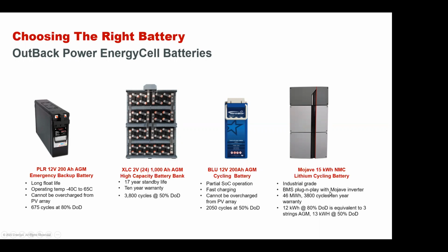The BMS makes a plug and play with the Mojave inverter. Basically, just hook up the 2 battery cables, the ground wire, and a CAN bus cable, and that's it. It's the only connections you have to make. We'll talk about that commissioning in just a moment. And then the 12 kWh at 80%, which is our recommended depth of discharge, is 12 kWh. That's equivalent to 3 strings of AGM batteries, which is about 13 kWh. So you get a little bit more kWh with 3 strings, but think of it as 3 strings of battery.